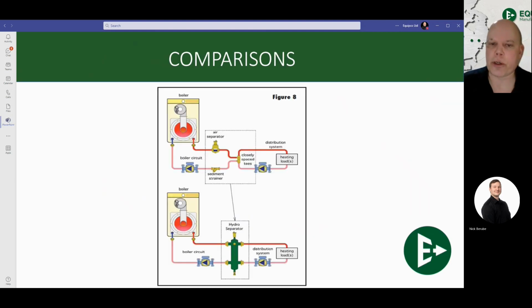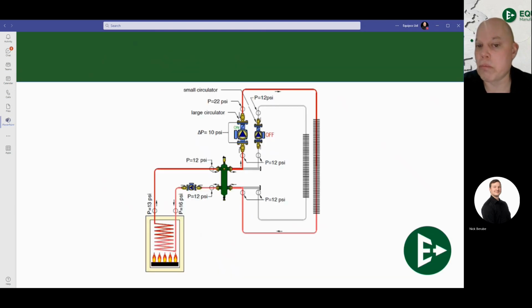And here's a great little picture of how you can take out the closely spaced tees, your air separator, and your sediment strainer or dirt filter, and replace the entire thing with a hydro separator, and it still makes that primary secondary system, which works extremely well for less fittings, less leak paths, less labor. It's going to be more effective and more efficient for everybody involved.